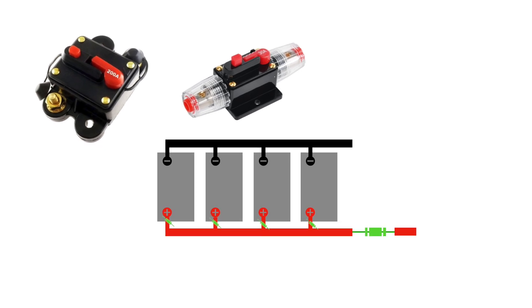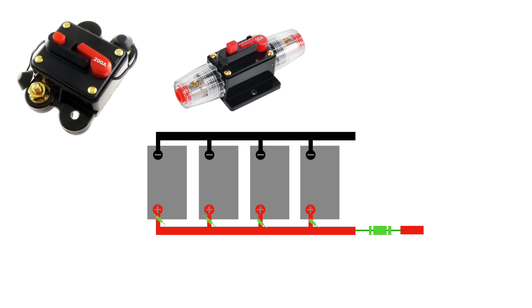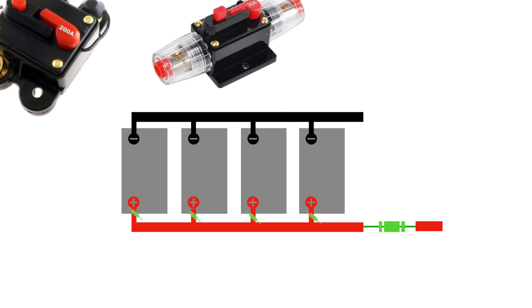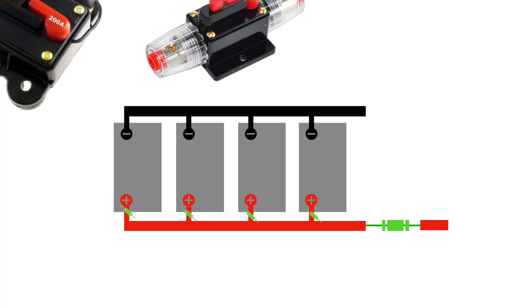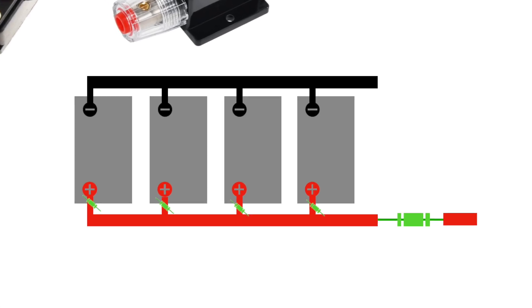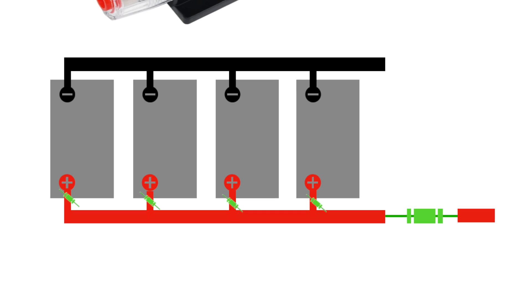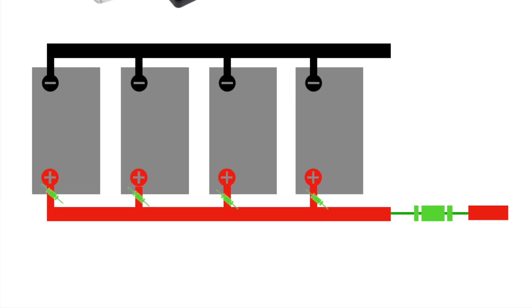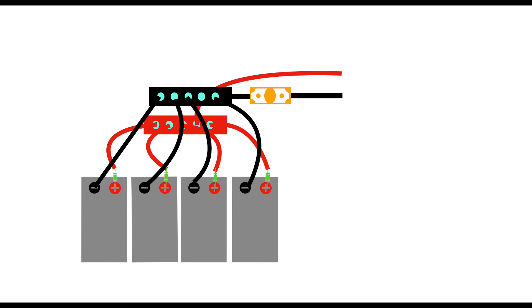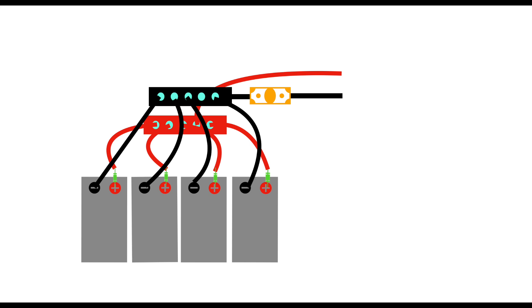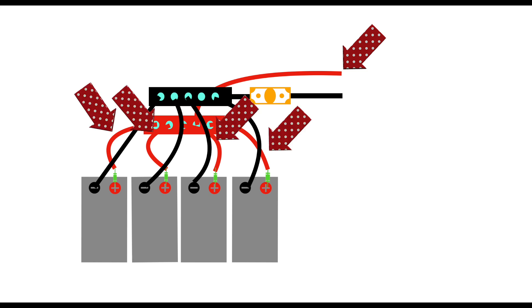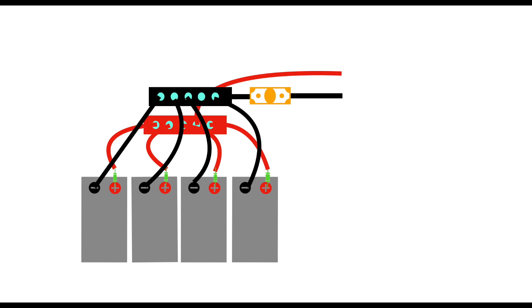You could do this with circuit breakers, but we believe that fuses are a much better solution - it's tidier and makes for a more compact design. We've seen circuit breakers that have not tripped out and nearly caused fires, so we tend to use fuses. If you're using individual conductors of the same length to keep all your batteries in balance, then you'll want to protect each individual conductor. Putting the fuses in this position also helps protect the BMS inside the batteries. Wherever you put the fuse, remember that it must be sized in accordance with the cable it's there to protect.